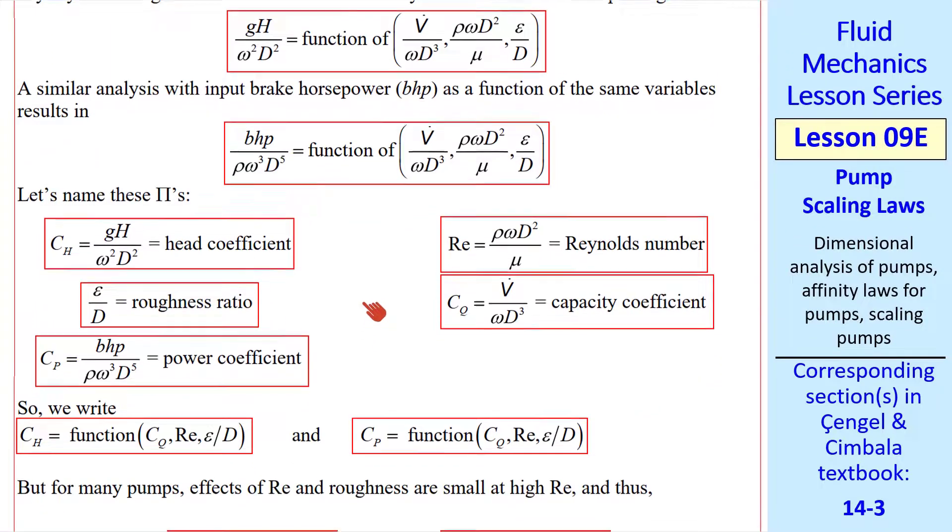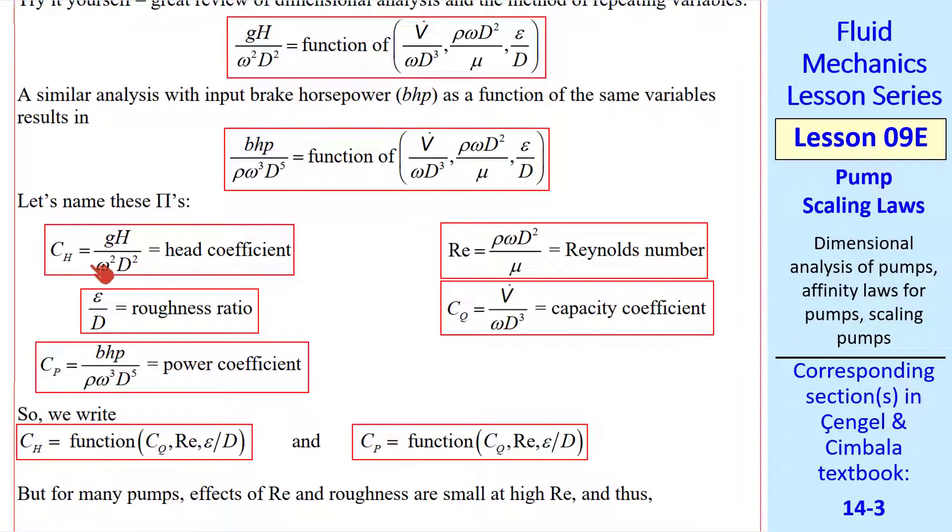The 3 independent pi's are the same, but the dependent one is now brake horsepower over rho omega cubed D to the fifth. In turbomachinery, we name these pi's. This first one is called the head coefficient, since it's a non-dimensional form of head. The second one is called the power coefficient, Cp, since it's a non-dimensional form of brake horsepower. This first independent variable is called capacity coefficient, which is a non-dimensional volume flow rate. We use Cq rather than Cv dot because in turbomachinery, Q is used instead of V dot typically as the volume flow rate. And this word capacity means volume flow rate in pump lingo. When a pump engineer talks about the capacity of a pump, he or she means the volume flow rate going through that pump.